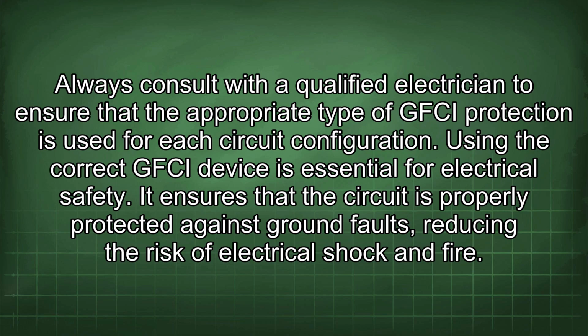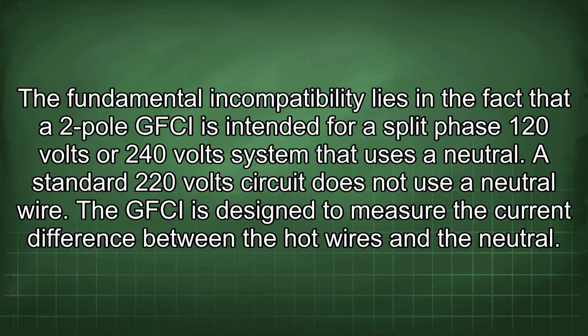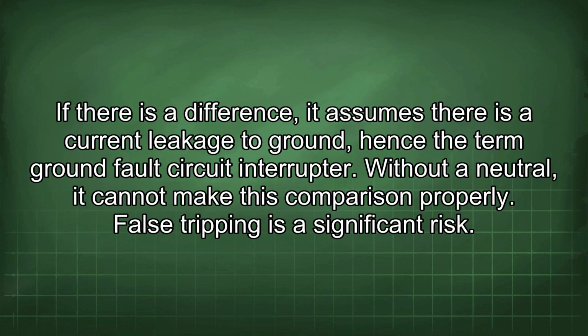It ensures that the circuit is properly protected against ground faults, reducing the risk of electrical shock and fire. The fundamental incompatibility lies in the fact that a two-pole GFCI is intended for a split-phase 120 volts or 240 volt system that uses a neutral. A standard 220 volt circuit does not use a neutral wire. The GFCI is designed to measure the current difference between the hot wires and the neutral. If there is a difference, it assumes there is a current leakage to ground, hence the term ground fault circuit interrupter. Without a neutral, it cannot make this comparison properly.